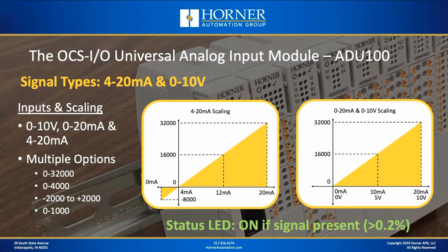And on the left there, I'm showing you how 4 to 20 milliamp readings come back. Now you'll notice that at 0 counts, that represents a reading of 4 milliamps, and 32,000 counts represents 20 milliamps. However, you can still detect values below 4 milliamps. They're just negative, all the way down to minus 8,000 counts, which represents 0 milliamps. So you can get high resolution by selecting the 4 to 20 milliamp range, but still detect under range or values below 4 milliamps.